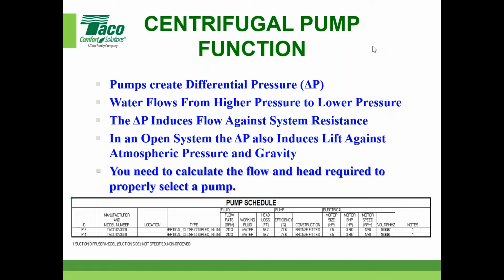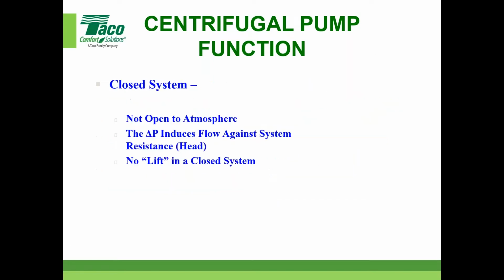So anyways, just some basic information you've got to talk about. I want to cover closed systems—chilled water type systems, cooling buildings through fan coils, the new craze of chilled beams or whatever, even through some air handlers. These are closed loop systems, not open to the atmosphere. That delta P induces flow against system resistance, but no lift.